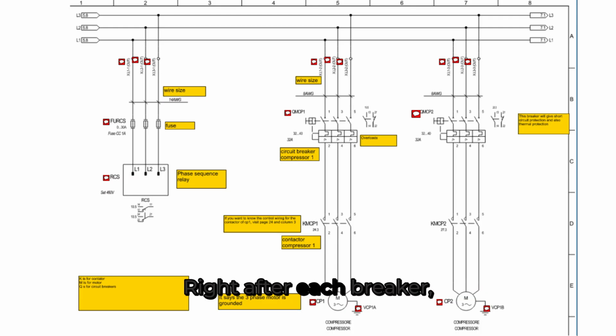Right after each breaker, we see the compressor contactor, with 8-gauge wire used for the compressor power wiring. Next to the compressor contactor, it is labeled that the control wire for the contactor is given on page 24, column 3. Finally, notice the reference at the top right of the page, column 8.